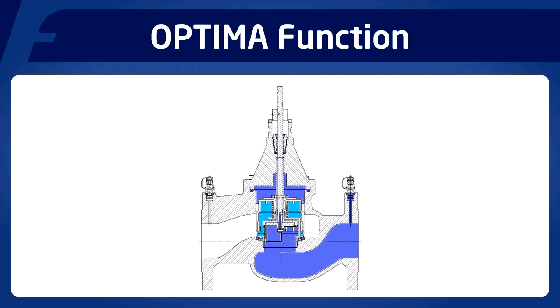and regulated as the actuator strokes the valve up and down, and some pressure is lost as it enters the valve. The pressure acts upwards on an area, creating a force upwards, which, due to the loss of pressure as the water flows into the valve, is slightly less than the pressure exerted downwards, and consequently an additional spring is included to enable a balance of forces.